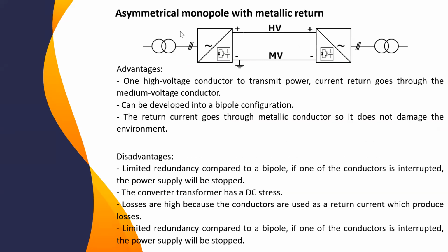For asymmetrical monopole, we have two types, metallic return and ground return. If we see here, for metallic return, we need only one high voltage conductor, while for the return path, we can use medium voltage. For this, the voltage polarity between positive and negative will not be the same. So for this, we need a special transformer. And then here, all return current uses the metallic return. So the advantage here, of course, is that we don't have a problem for the environment. The disadvantage here is that in case one conductor fails, the power will be interrupted.